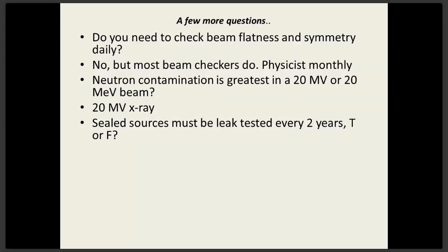But if a sealed source like cesium-137 or radium is going to be used, it has to be tested at a certain interval. Is it every 2 years? True or false? False. It has to be tested every 6 months. So a reusable source like cesium or radium has to be tested for leaks every 6 months if you're going to continue to use that. Iridium, like I say, doesn't have to be leak tested because it's changed every 3 months. So that eliminates the need to leak test it.